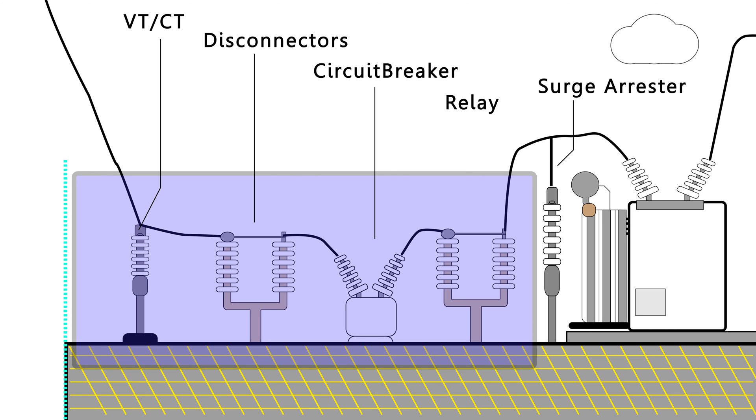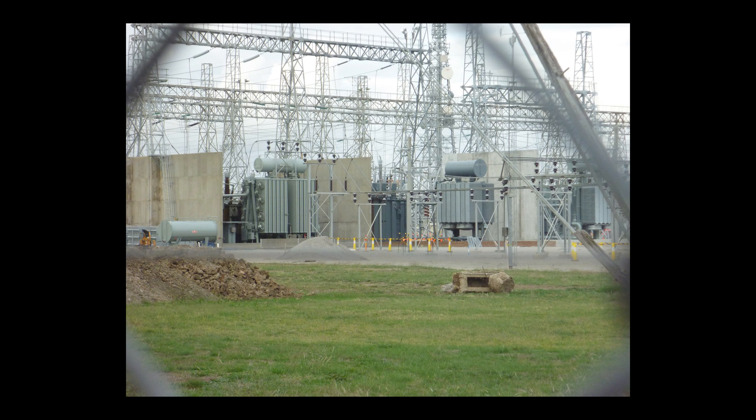There's also one other type of asset which is important. This is called the surge arrestor. The job of the surge arrestor is to protect the transformer and other parts of the substation against high frequency surges such as lightning strikes and switching surges. The conventional protection system isn't fast enough to protect against lightning strikes and switching surges. So all these assets together are called the protection system.